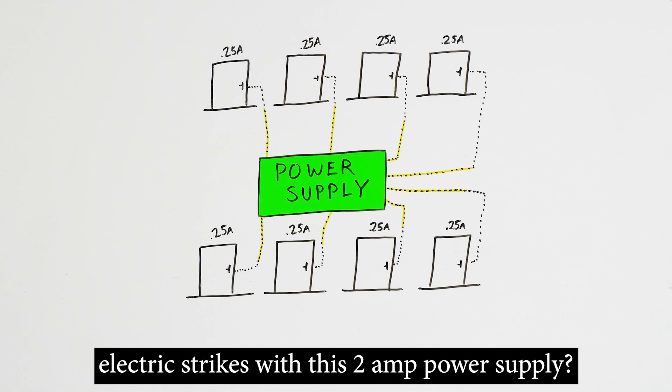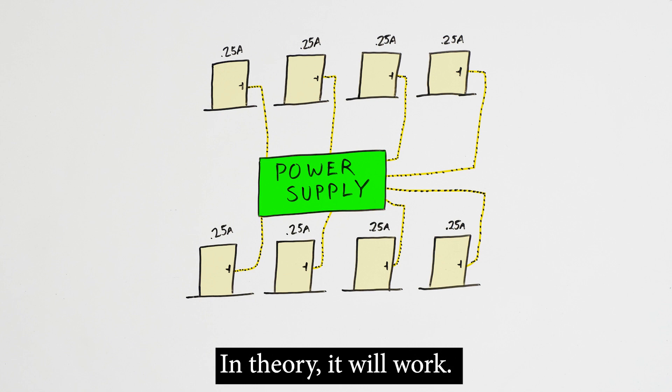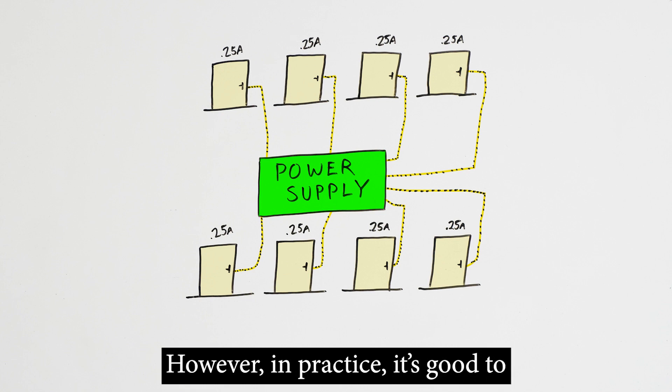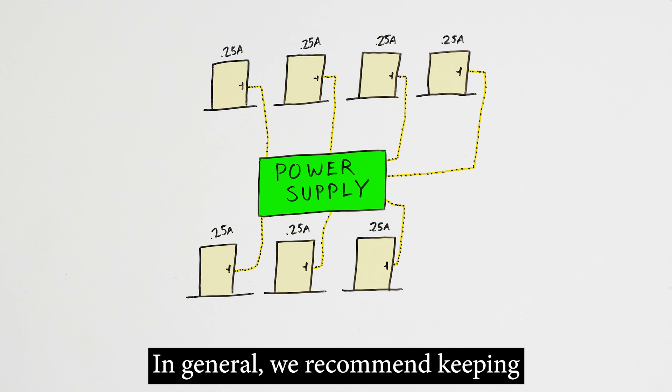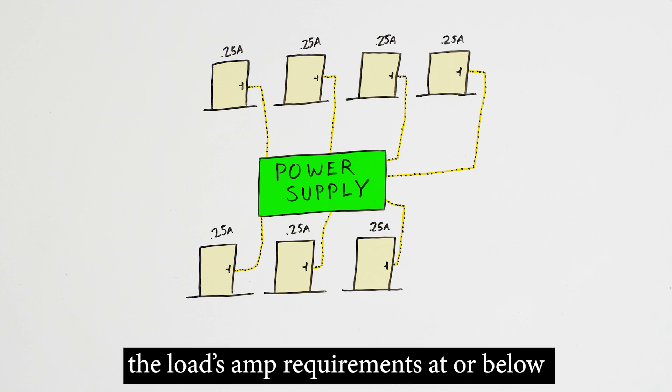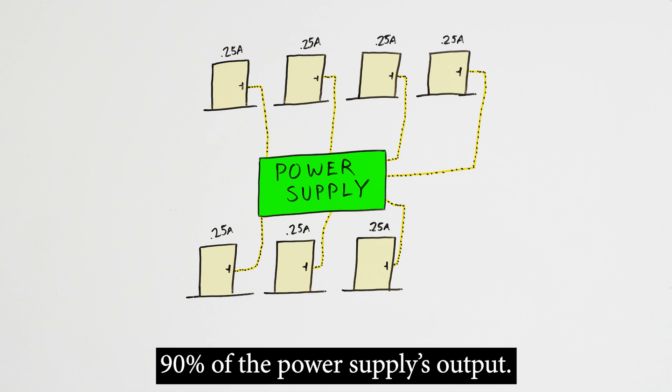What if you wanted to power 8 electric strikes with this 2 amp power supply? In theory, it will work. However, in practice, it's good to have a little wiggle room. In general, we recommend keeping the load's amp requirements at or below 90% of the power supply's output.